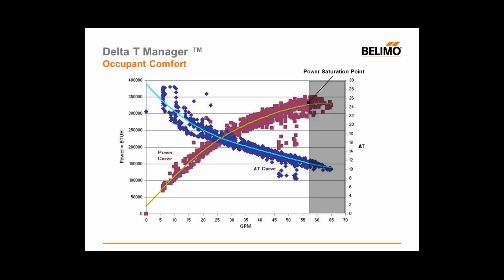And again, when we talked about the overflow, when we talked about generating low delta T, we said that that functionally caused 3 problems. One of them was we pumped too much water. The second one was that we had a low delta T problem. And the third one was that we produced no additional BTUs. So if we're able to just slice off the portion of the curve where no more BTUs are produced, well, then we shouldn't have any adverse impact on room comfort. And again, you have to make an educated and smart decision about setting your delta T set point so that you won't run into this type of trouble.